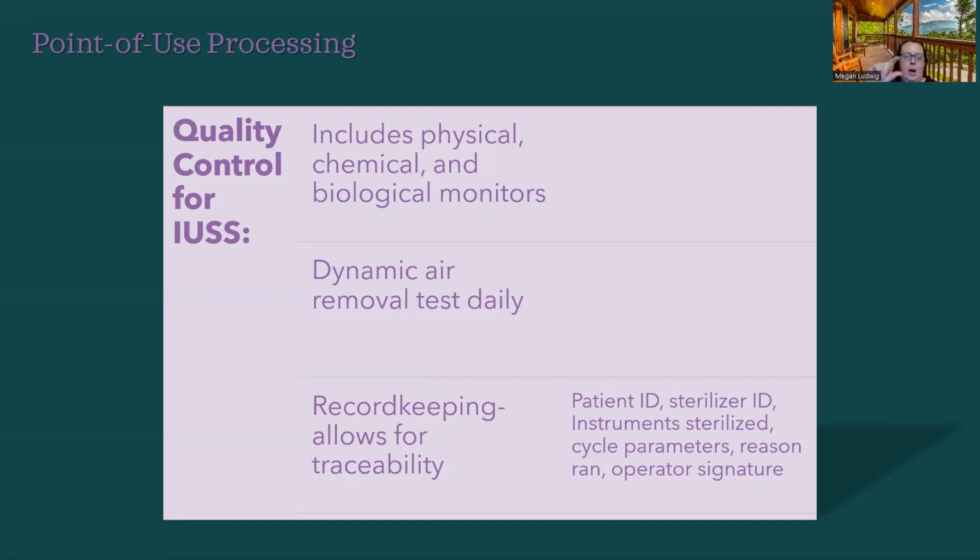It's usually a little vial that contains a type of spore-forming bacteria that is hard to kill. You want it in that load. Then, depending on the type of monitor, it can be read in a couple hours if it's rapid, or 24 hours.